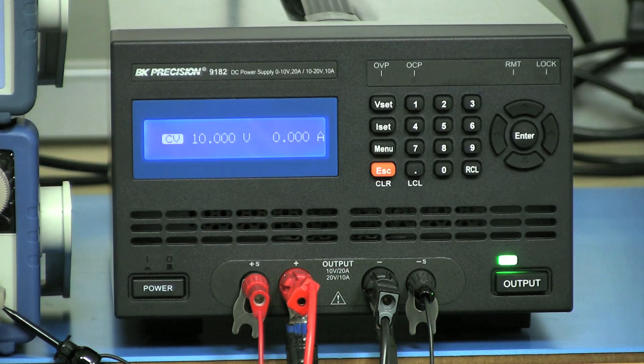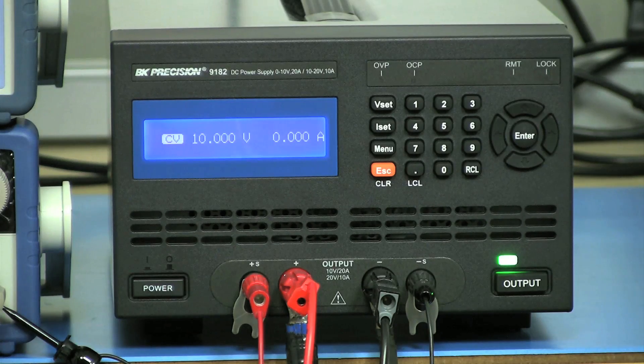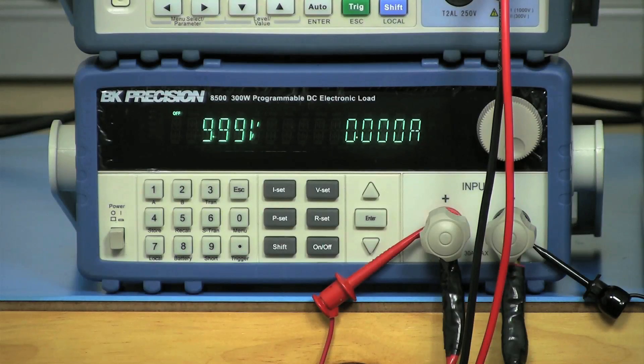For setup, I have the 9182 connected to the 8500 from positive to positive, negative to negative terminal. Because the current will be as high as 20 amp, be sure to use wires with at least 14 AWG wire gauge.